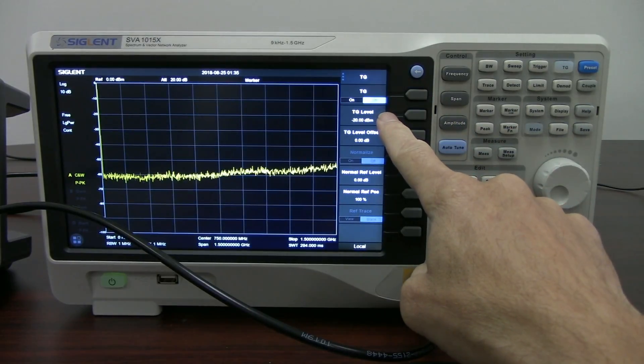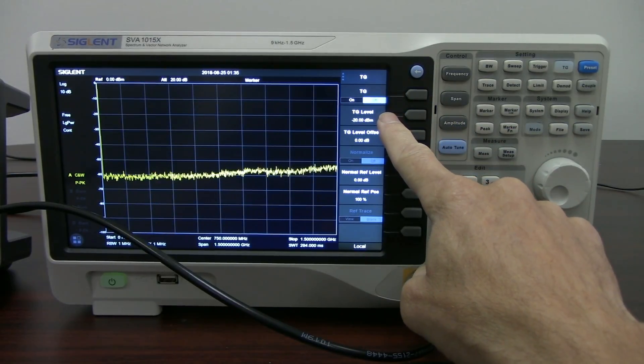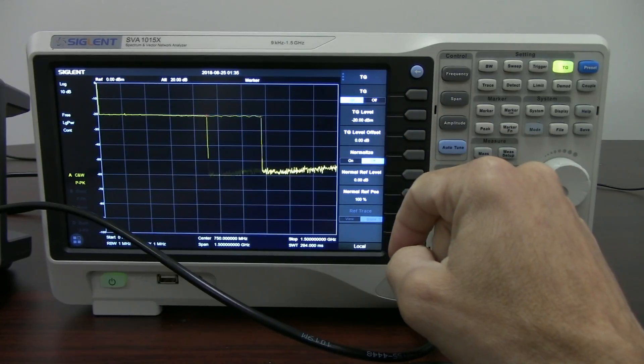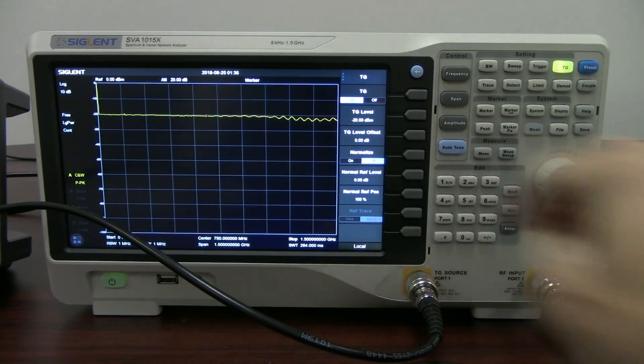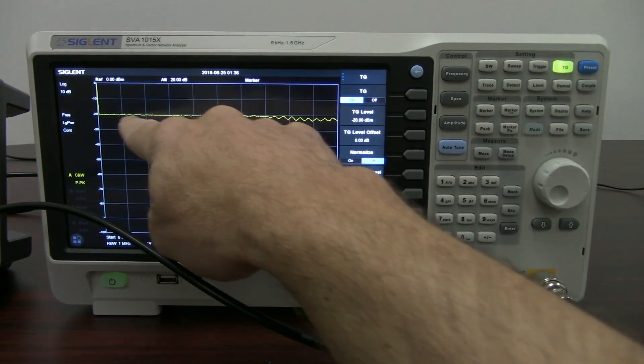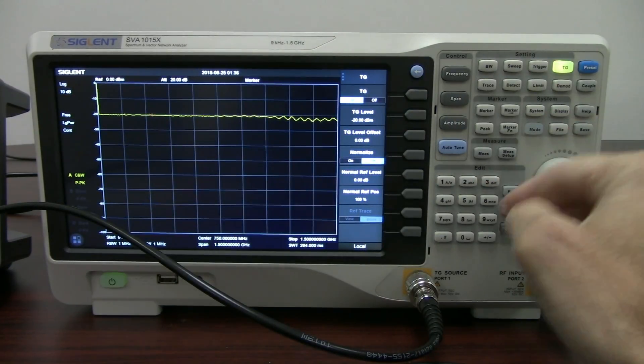And you'll see that the tracking generator level is set to minus 20 dBm. So when we turn on the tracking generator, lo and behold, we've got a line right here coming across about minus 20 dBm. A lot of the ripples and things that you see are totally normal. They're within specifications.